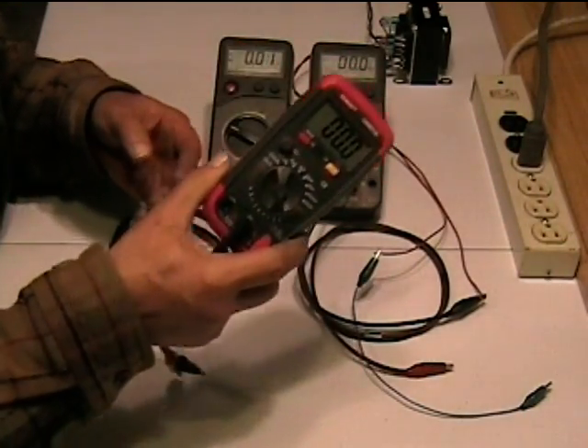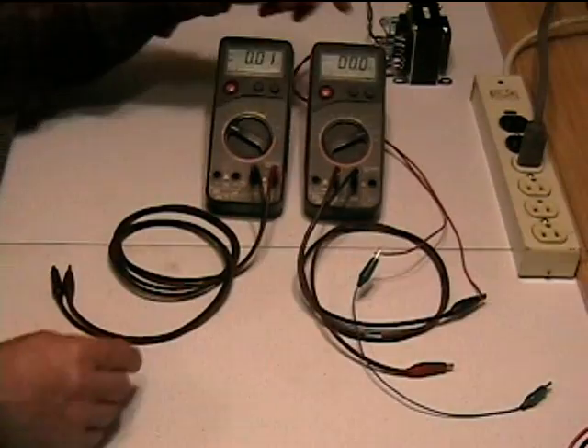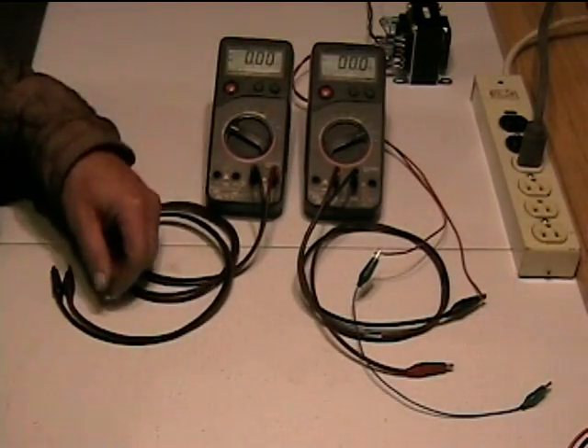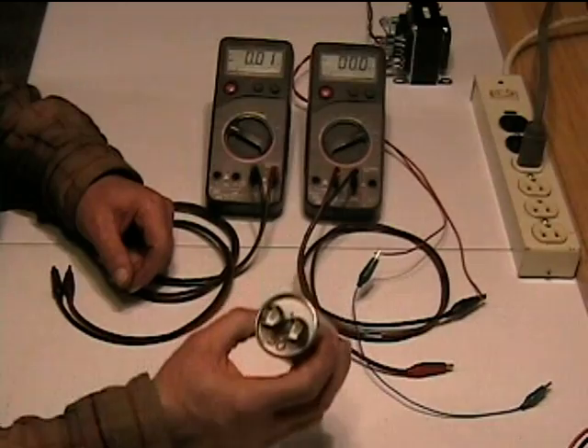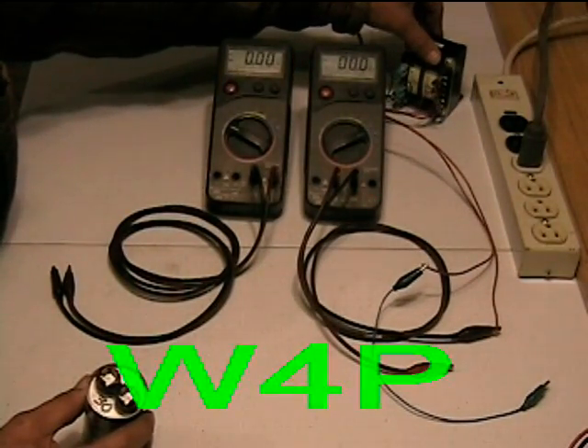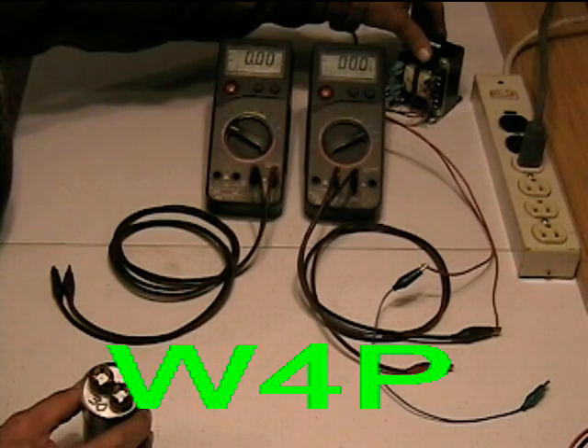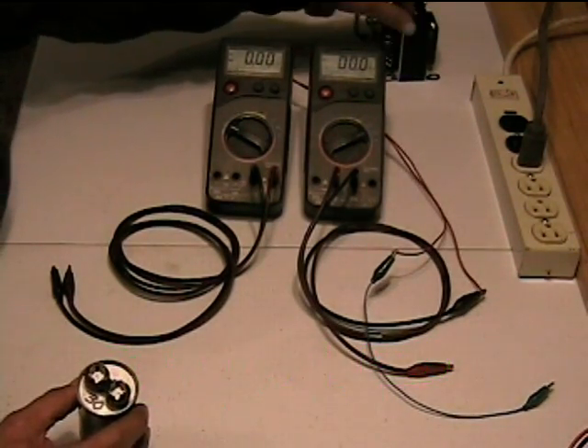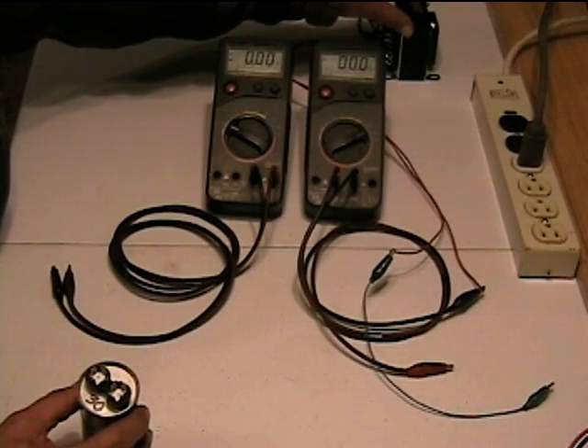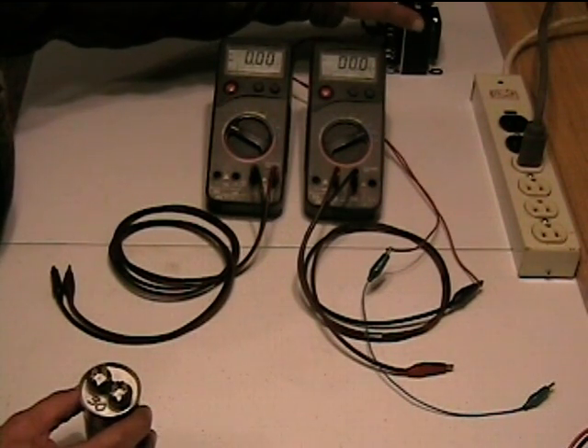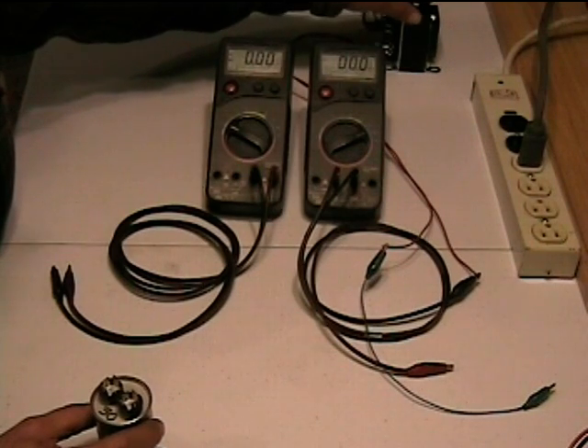But if you don't happen to have one of these, but you do have a meter that'll measure AC amps and volts, you can measure this capacitor using a source of AC voltage. I use a transformer, which provides me a low voltage AC source, which is isolated, so it's safe to work with. This transformer puts out 18 volts AC or so, and it's good for about 4.5 amps, so it'll handle a pretty good sized capacitor.